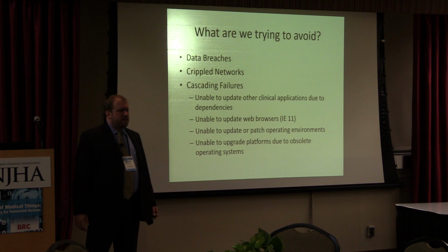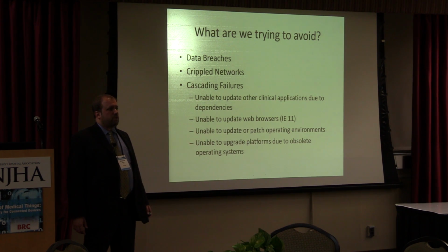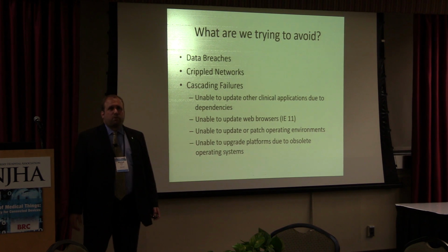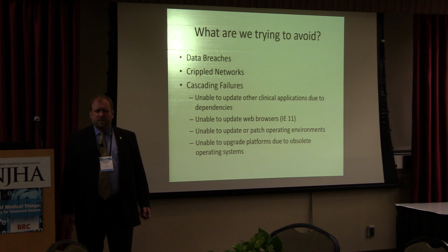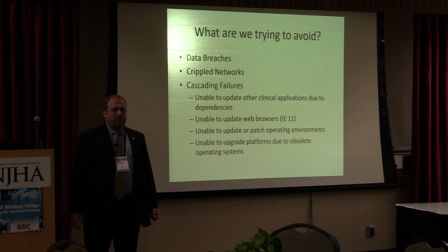You have some applications out there that still need Windows XP. I will tell you, we did a vendor review of a certain very large manufacturer, and I got their MDS2 form. I called the person up at the company whose name was on that form. I said, do you understand that device runs Windows XP and that there is no way we are going to allow that onto our network?